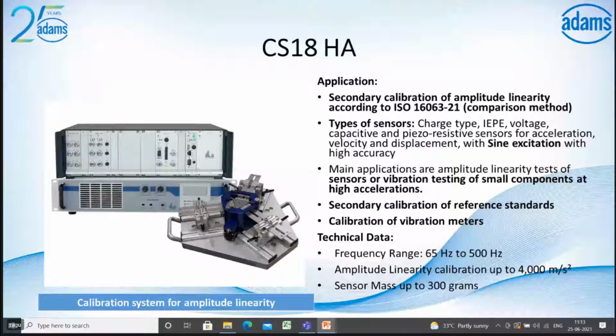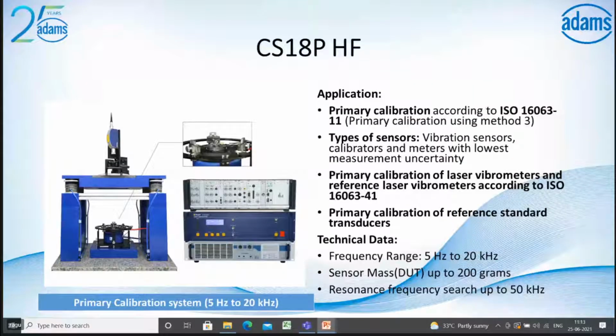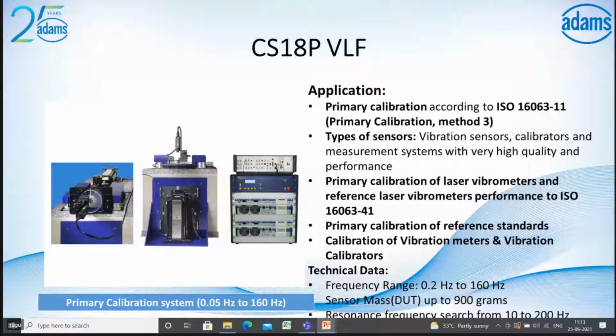The CS18P is a primary calibration system for high frequency, according to ISO standard 16063. Here you can calibrate reference standard transducers, and do primary calibration of laser vibrometers and reference laser vibrometers according to ISO 16063-41, from 5 Hz to 20 kilohertz. And the CS18P is also a primary calibration system for very low frequencies according to ISO 16063. The sensor types are vibration sensors, calibrators, laser vibrometers and reference standards.